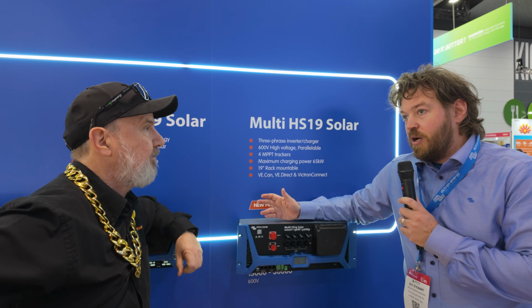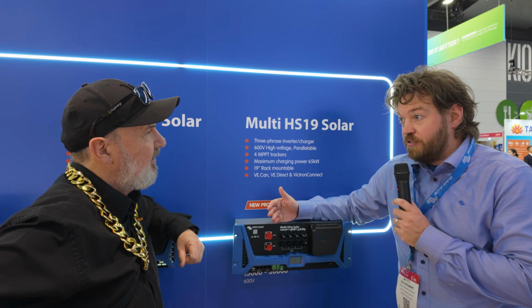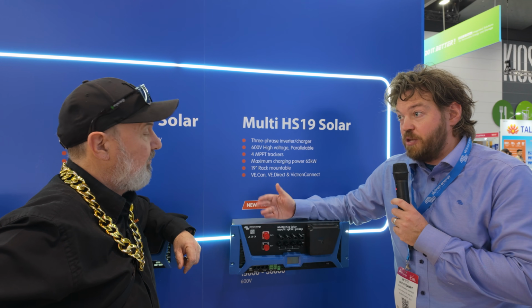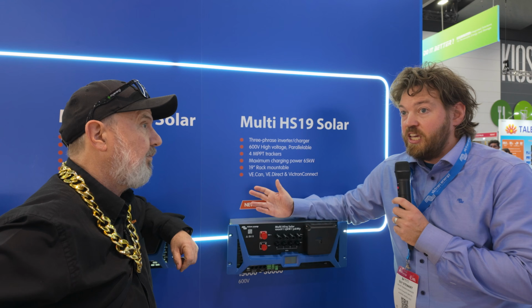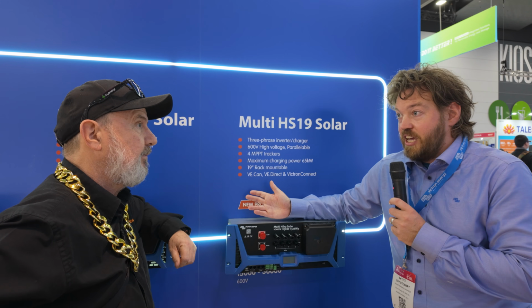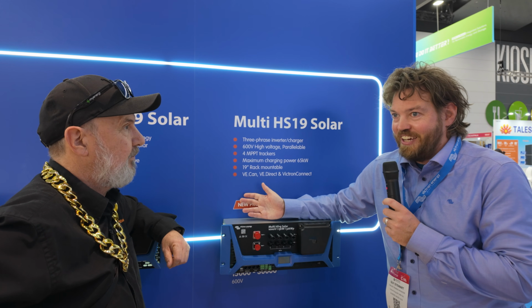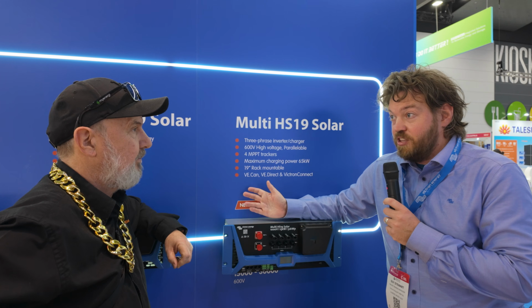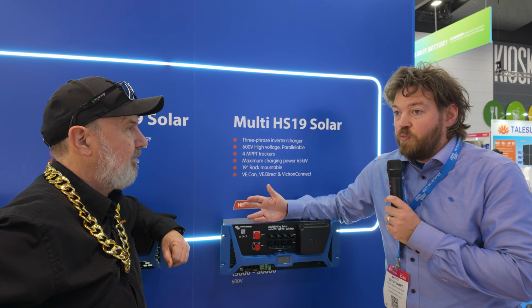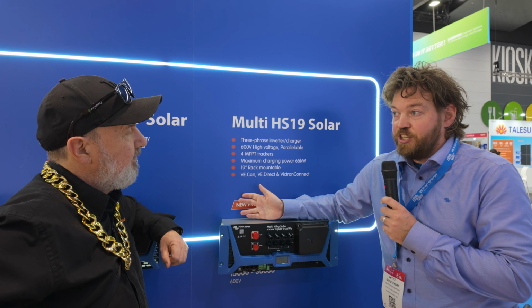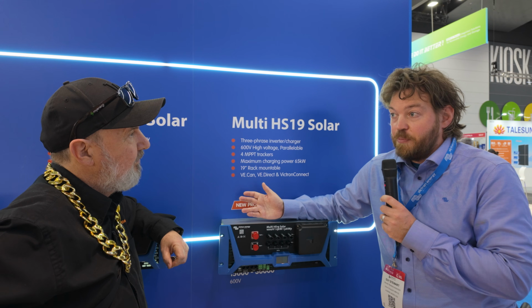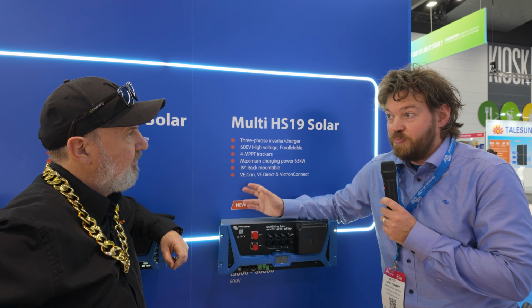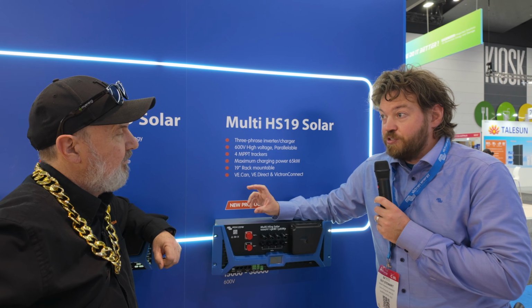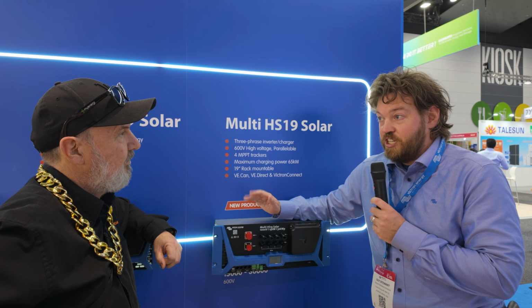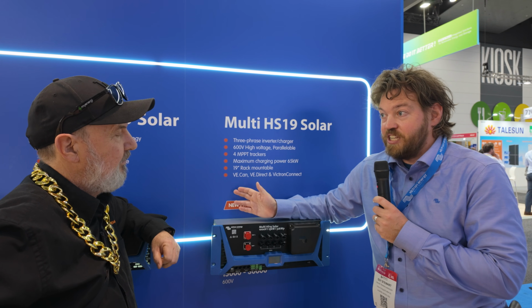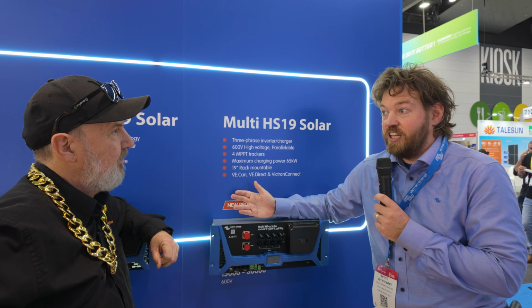A lot of products in the market are at 400 volt. This is 600 to 800 volt on the battery side, which makes it an early entrant to market, even though it's not in the market yet. There aren't that many batteries supporting those voltages. One thing to be aware of at those voltages is most battery suppliers' capacity is very large, because they're often supplying 48 volt modules and you need to stack them up in series to get to that higher 600 to 800 volt operating range, which means very large systems.